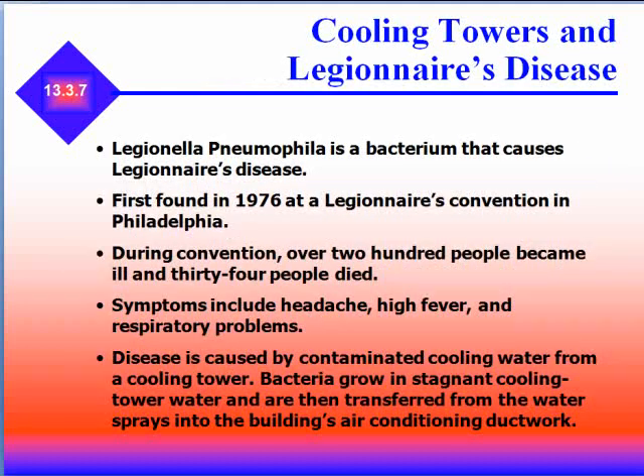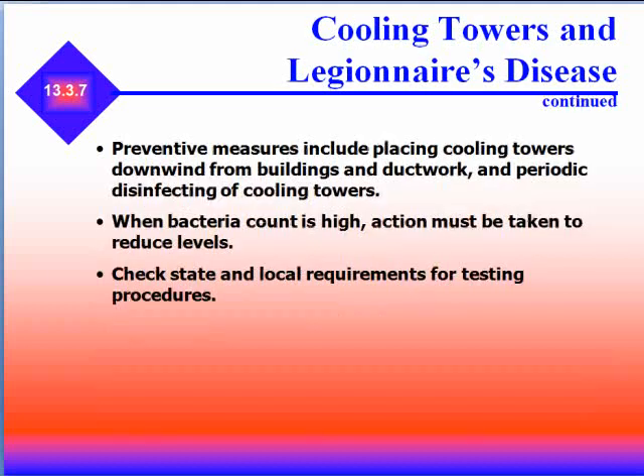One issue with cooling towers is Legionnaires' disease. Legionella pneumophila is a bacterium that causes Legionnaires' disease. It was first found in 1976 at a Legionnaires' convention in Philadelphia, where over 200 people became ill and 34 people died. Symptoms include headache, high fever, and respiratory problems. The disease is caused by contaminated cooling water from a cooling tower — bacteria grow in stagnant cooling tower water and are then transferred via water sprays into building air conditioning ductwork. Preventative measures include placing cooling towers downwind from buildings and ductwork, and periodic disinfecting of cooling towers. When bacteria count is high, action must be taken to reduce levels, and it is mandatory to check state and local requirements for testing procedures.